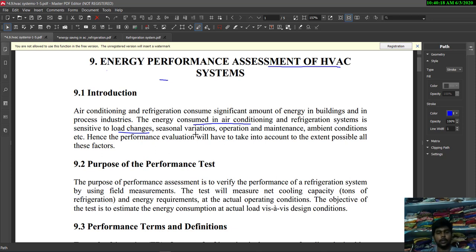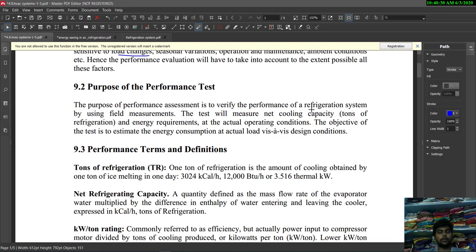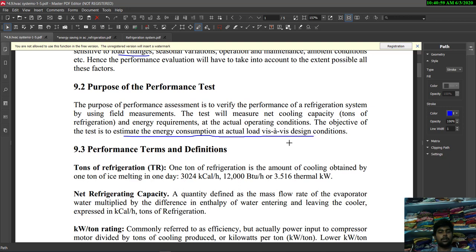Hence, performance evaluation must account for all these mentioned factors. The main purpose of the performance test is to verify the performance of the refrigeration system using field measurements and test conditions such as net cooling capacity in tons of refrigeration, at actual operating conditions. The objective of the test is to estimate the energy consumption at actual load and design conditions.